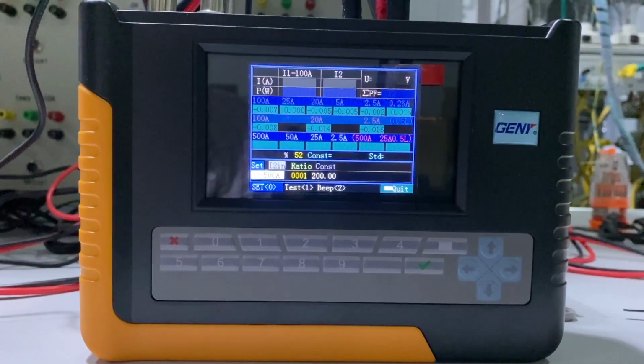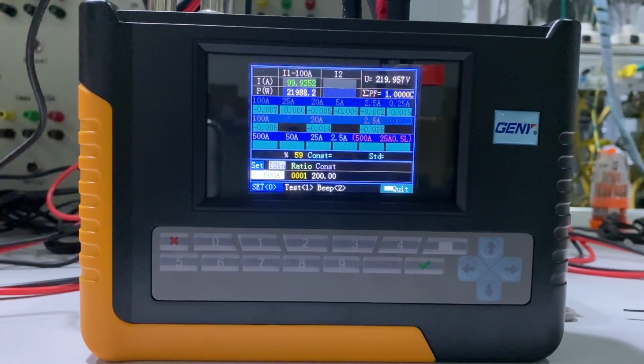After the calibration parameter is set, we can start at the first calibration point. The first calibration point is 220 volts, 100 amperes, power factor 1. Inject voltage and current. It starts by counting the pulses from the reference meter and calculating the energy error.